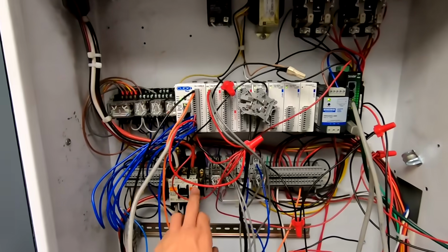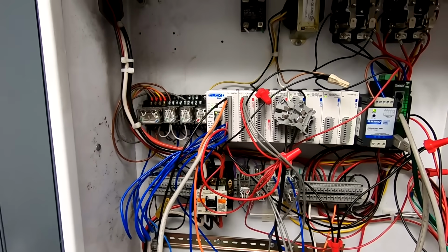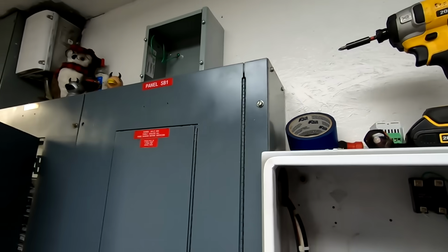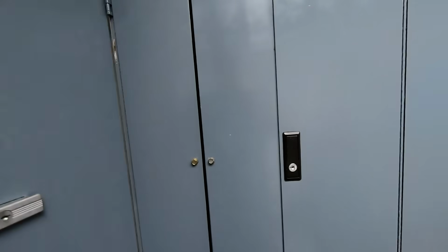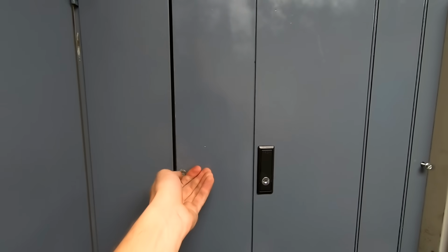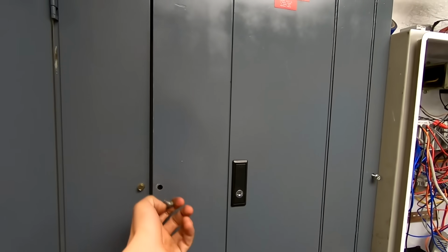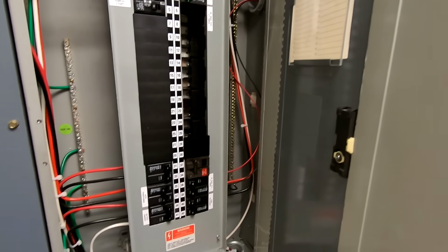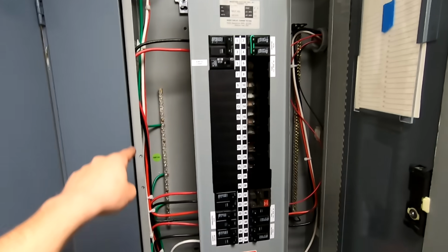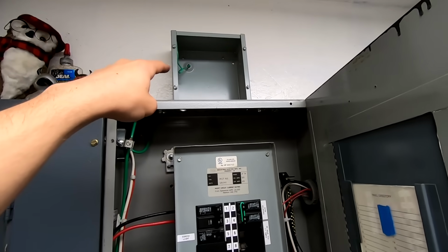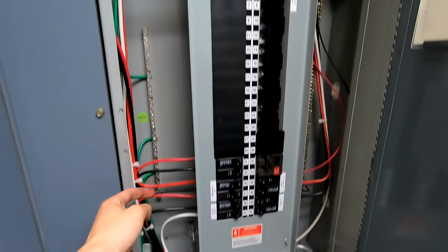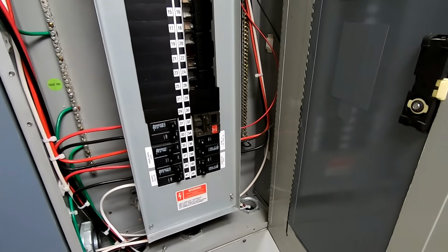Chances are when I change this to the DC contactor, I'll throw it in this can up here above panel SB1, which is my split bus panel. And if I take this screw out, I've already been in here planning this out. I'll just chase my generator feeds up through the side into that can with the contactor, and then back down into my generator main breaker.